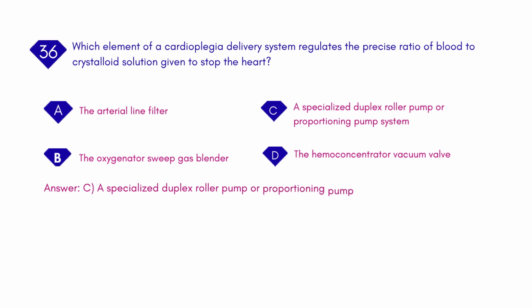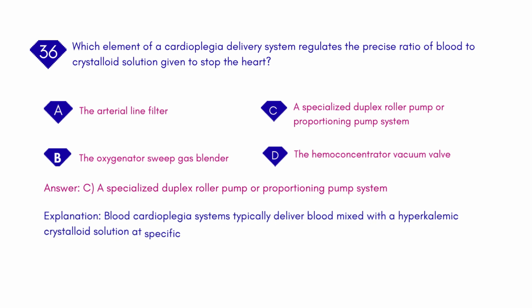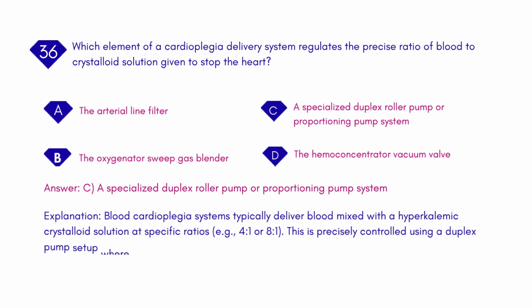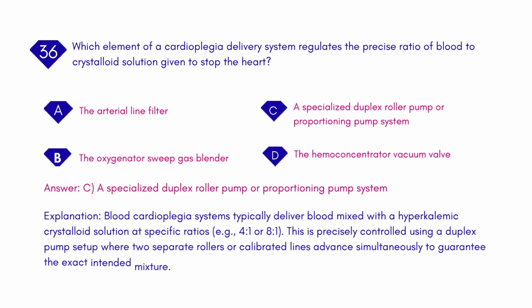Answer: C. A specialized duplex roller pump or proportioning pump system. Explanation: blood cardioplegia systems typically deliver blood mixed with a hyperkalemic crystalloid solution at specific ratios, e.g., 4:1 or 8:1. This is precisely controlled using a duplex pump setup where two separate rollers or calibrated lines advance simultaneously to guarantee the exact intended mixture.